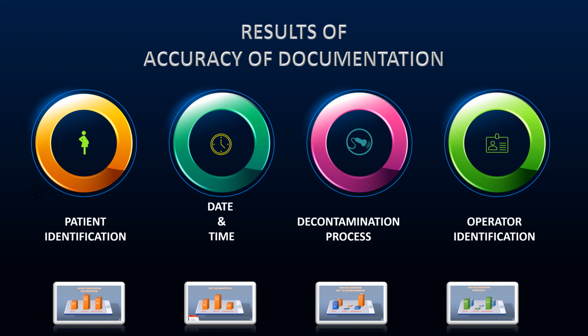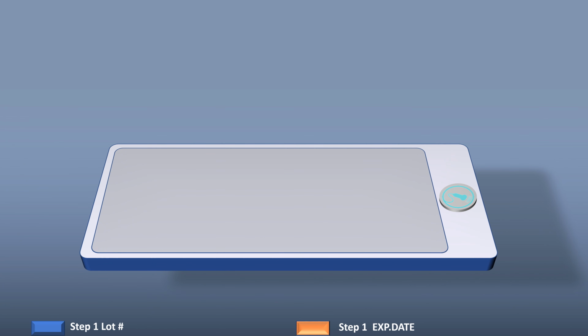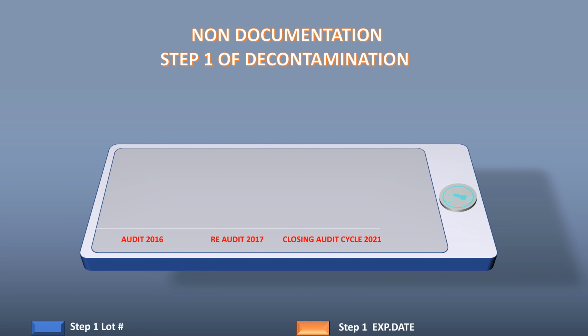Results of accuracy of documentation, clinical audit. Regarding non-documentation of step 1 of the decontamination process, step 1 lot number: the non-documented data regarding lot number in 2016 was 8%, while it was 0% non-documentation of step 1 lot number in 2017. In the 2021 closing audit cycle, non-documentation of lot number step 1 was 3%.